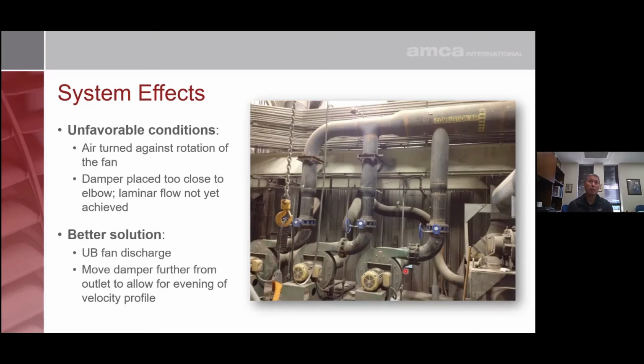That's 2,000 pounds. Every 3 minutes, you're moving 6,000 pounds of air through that fan. You're functionally moving a large vehicle through that fan every 3 minutes. That's a lot of mass. And just like if you're driving down a twisty, turning road, it's going to take you a lot longer to get down that road. It's going to be less efficient than if you have a straight road. And if you have good bends in that road, that's going to improve the efficiency of that vehicle as it drives. And we have to remember that when we're moving air, we're not moving 0.075 pounds of air through a fan. We're starting to get into thousands of pounds, if not tonnage of air, as it's moving through there. And we have to be cognizant of that.